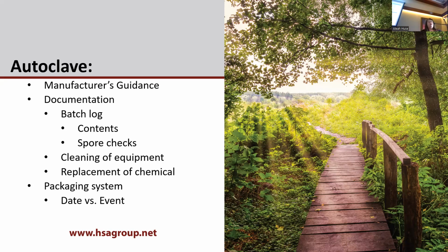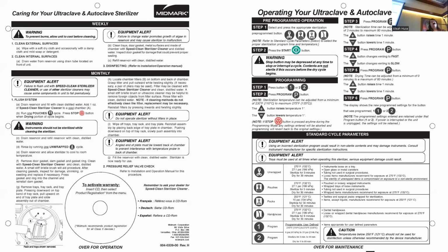Here's an example of a very common autoclave manufacturer's guidance. This is the synopsis version. Usually the guidance is probably a good manual size long, but this is just an example of what you would want to look at. And you can see it has weekly, so I should be able to see documentation you're hitting what that weekly requirement is. They have monthly tasks, and again, I should see that monthly log that this is being kept and measured. And then your process to the right is how to actually run the autoclave machine.